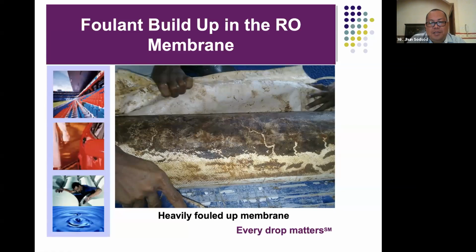Just to share my experience with this particular RO membrane: we received a complaint from the end user about feed pressure increase, delta P increase, and production decline. This is from a wastewater recycled RO. In our initial discussion, we explained it is very possible that fouling is causing the main issue, but their argument was that since they have UF, the tendency of fouling should be very minimal, almost nil.